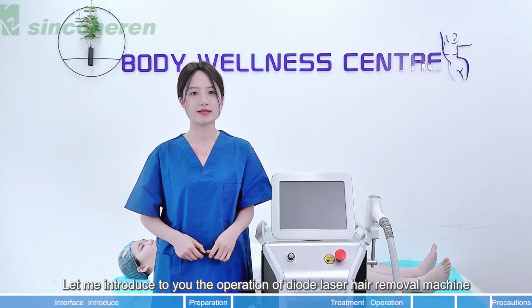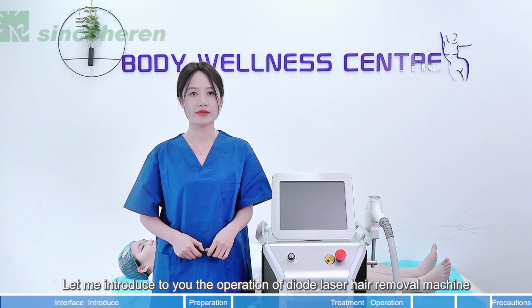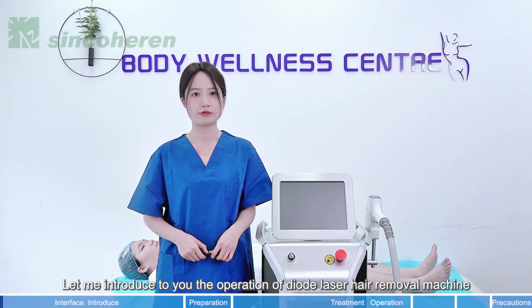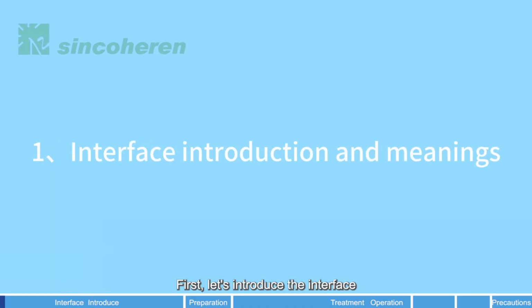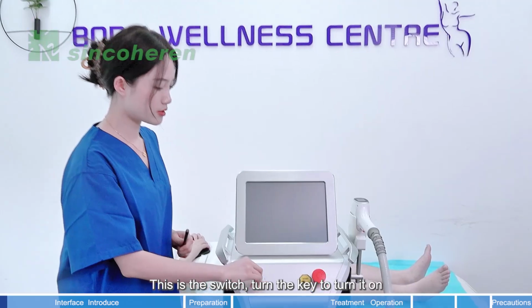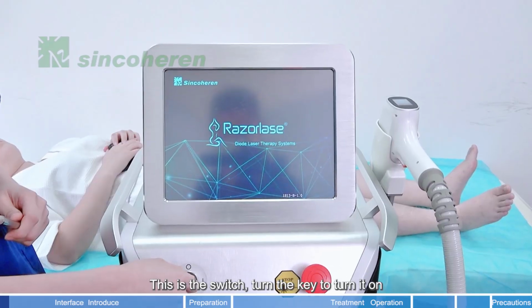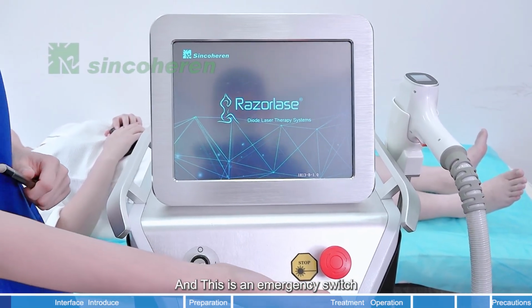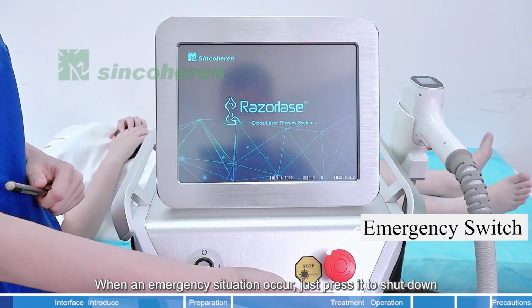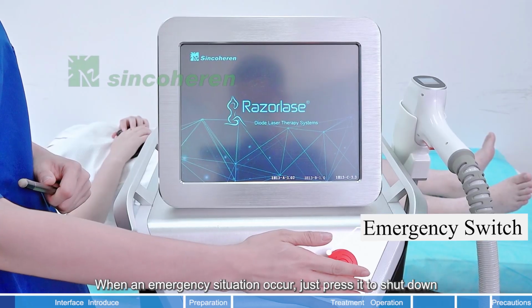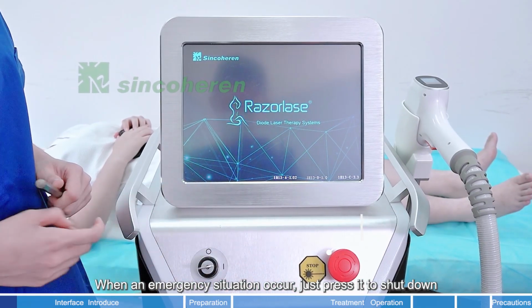Hello everyone. Let me introduce to you the operation of the diode laser hair removal machine. First, let's introduce the interface. This is the switch, turn the key to turn it on. And this is an emergency switch. When an emergency situation occurs, just press it to shut down.